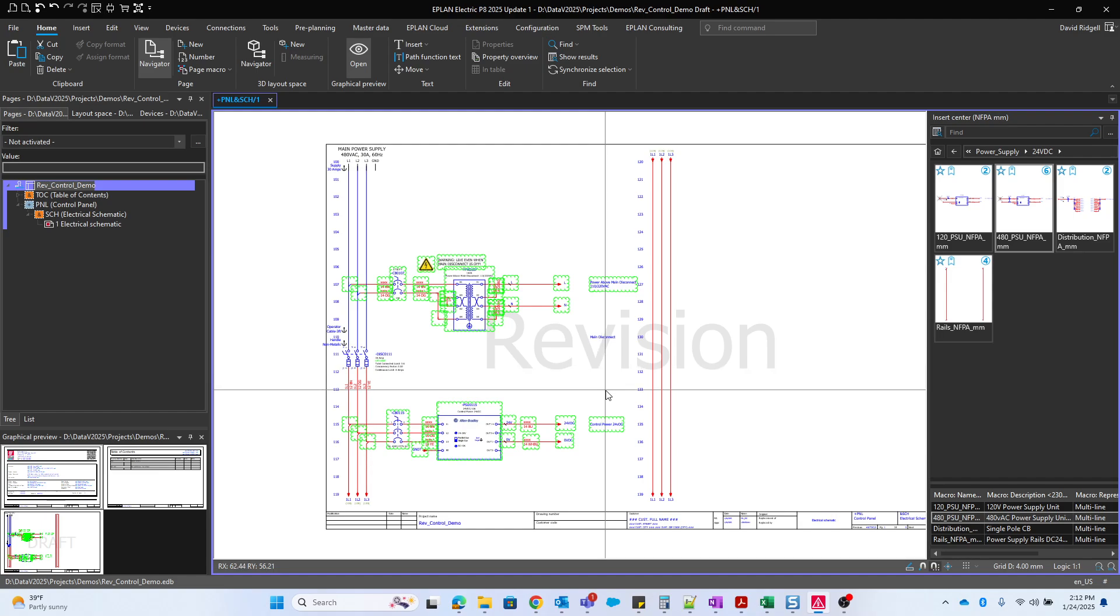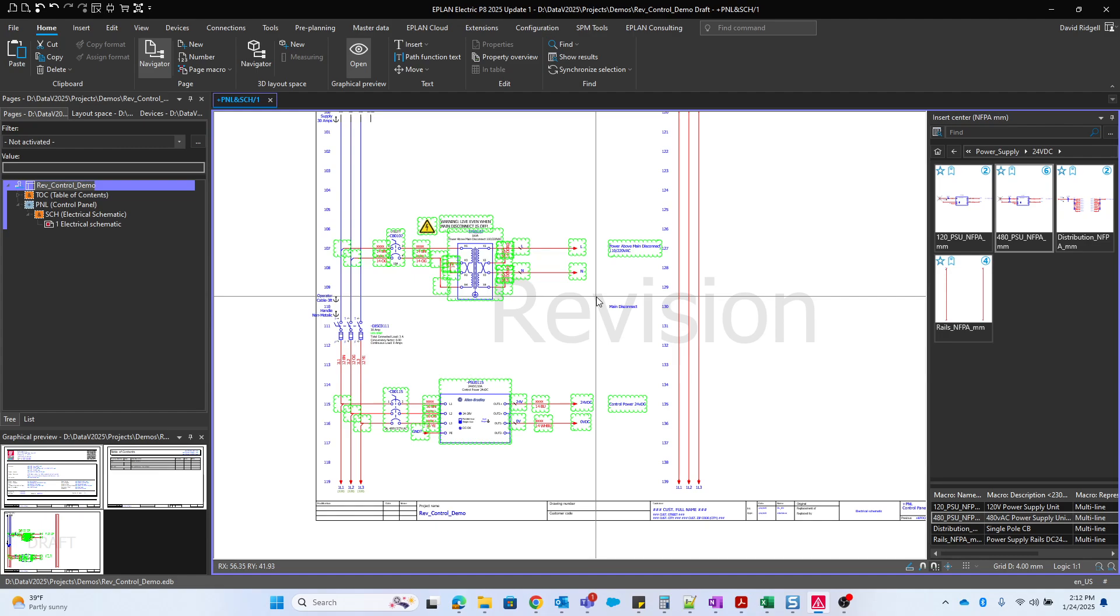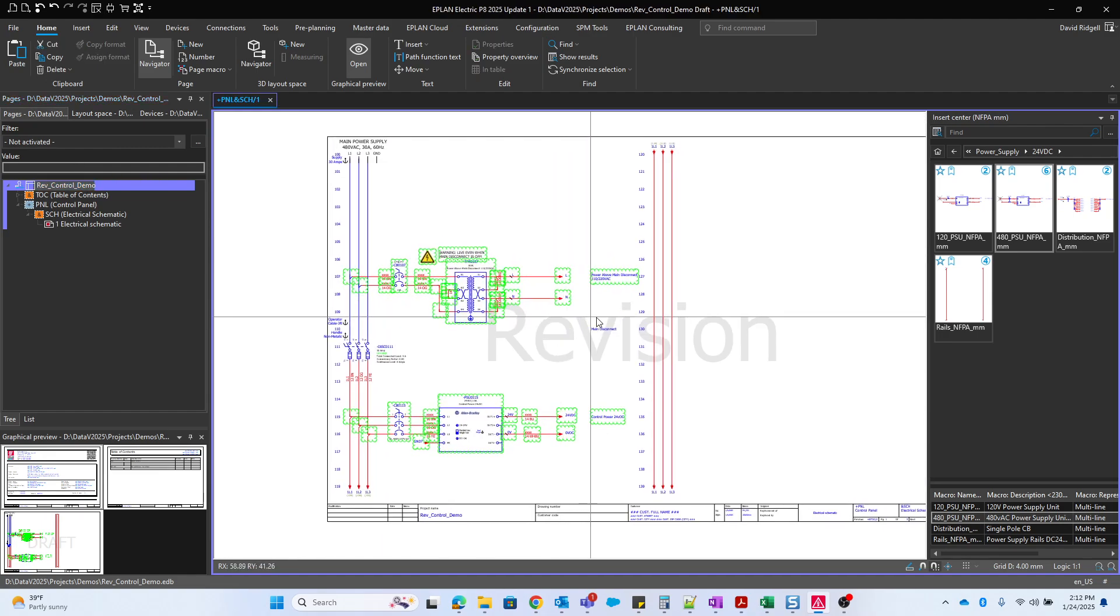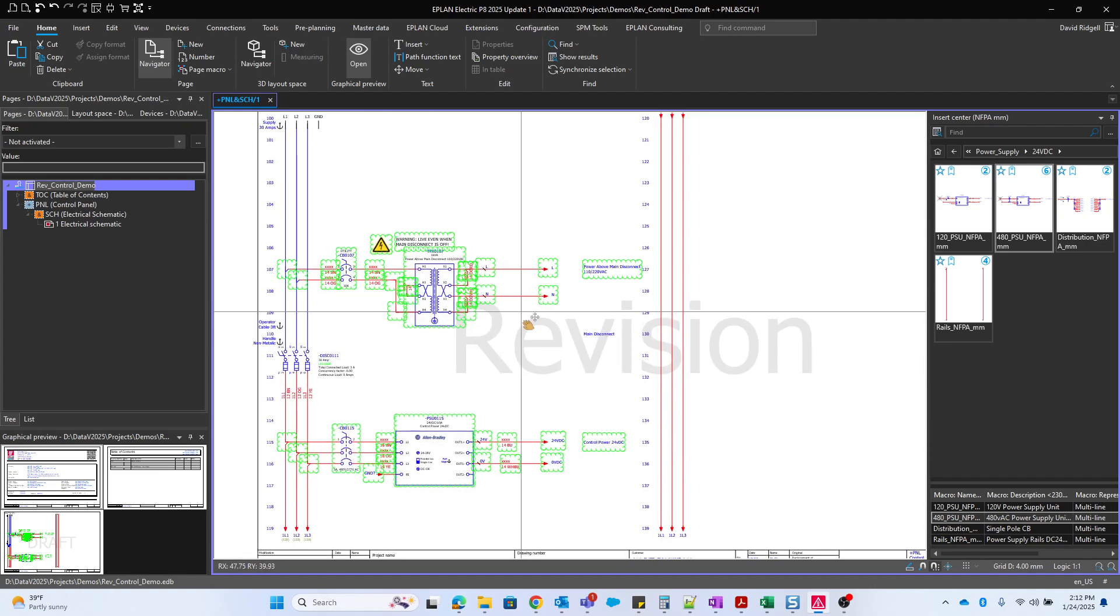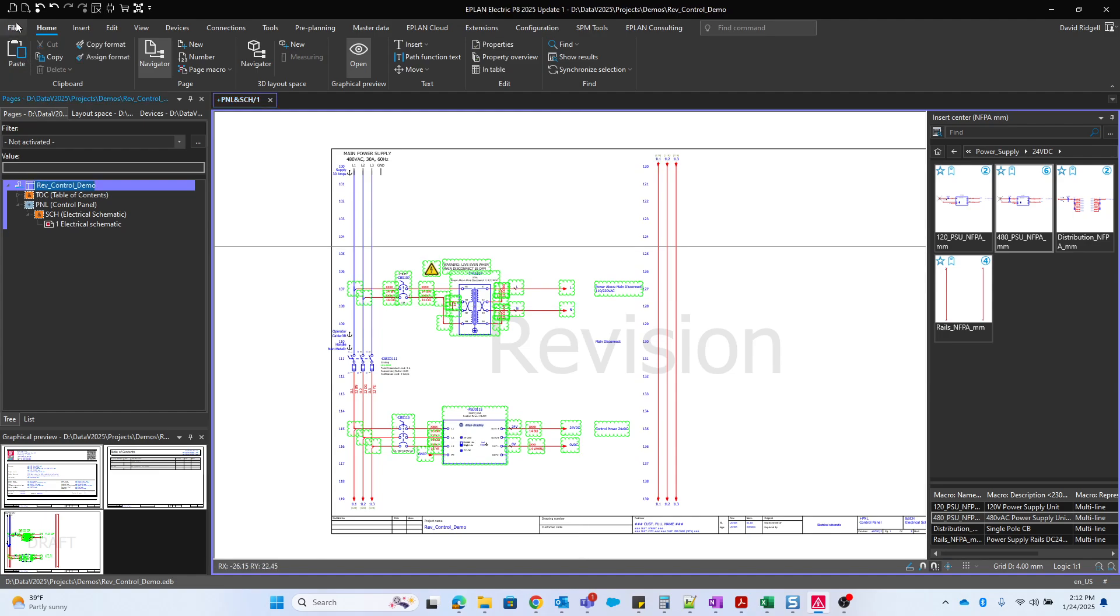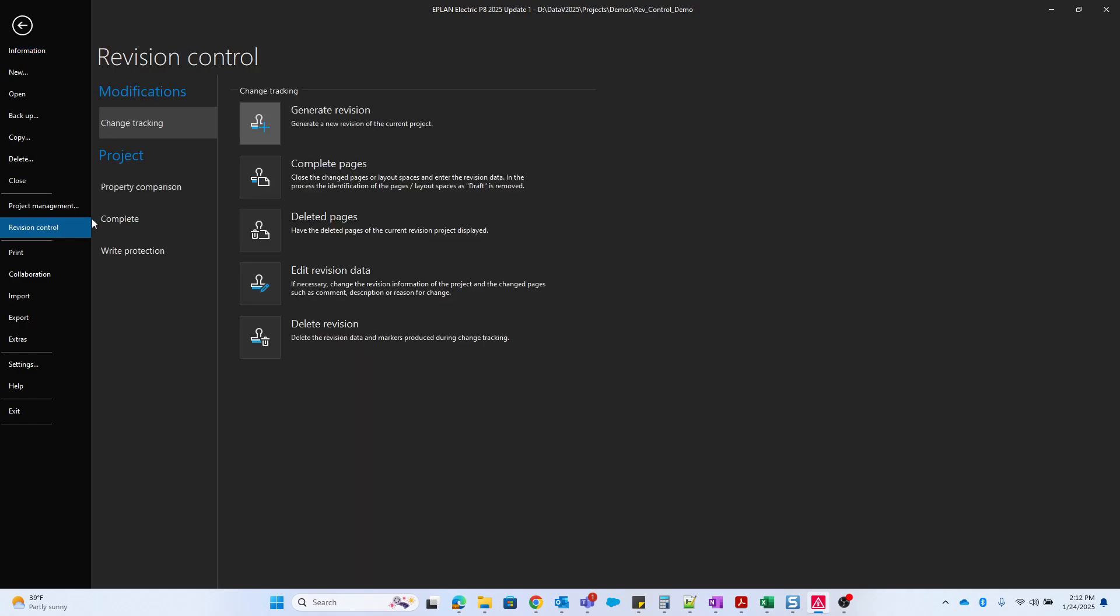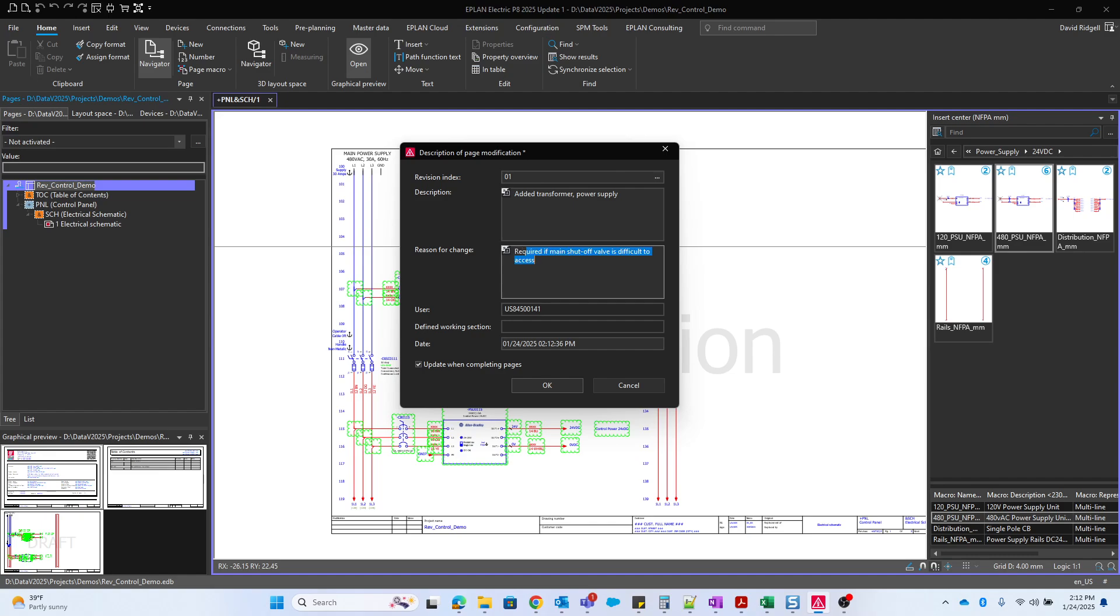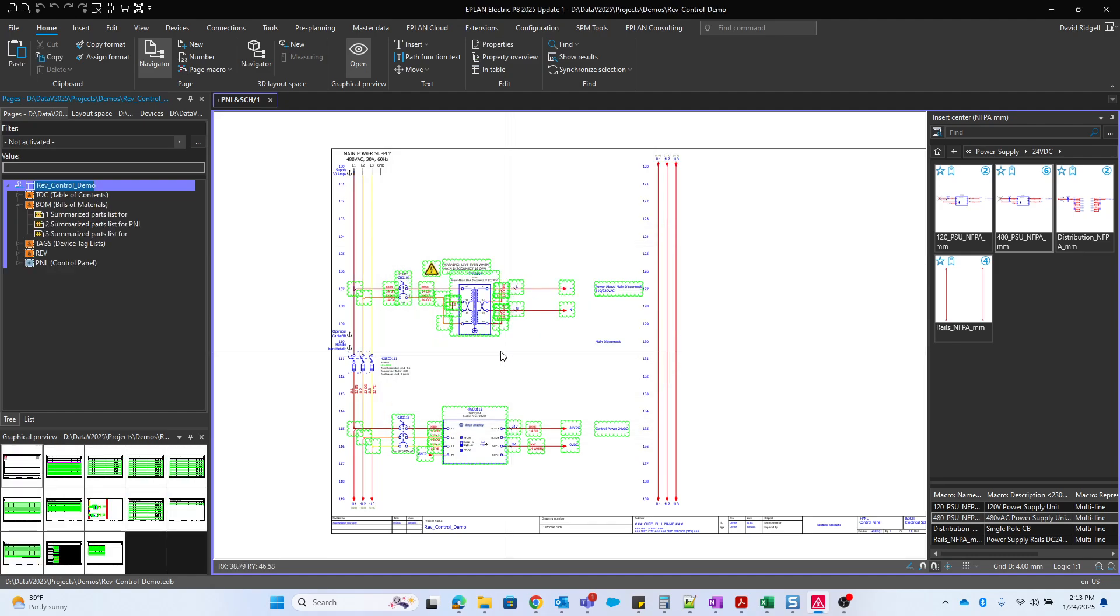Next, let's say that we've made all of our changes and we feel good about the progress of the project. We want to resubmit it in for approval. So now what we're going to do is complete the pages. What this will do is it'll put a revision index into the page properties and it will clear this watermark for us. So I'll go back to file, revision control, and complete pages. It's going to ask about the revision index. I'll put one, add a transformer, power supply, reason for change, request from customer. And we have this checkbox update when completing pages. This will actually generate and update the reports.